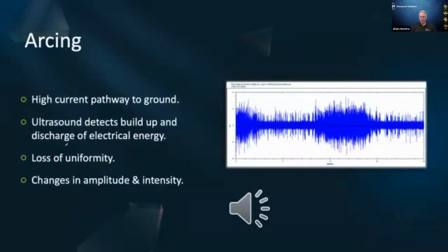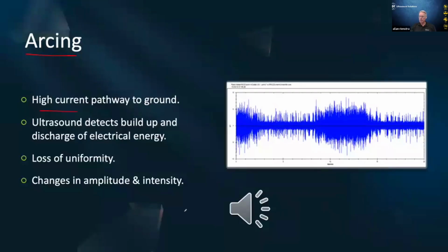I'm showing progressions here. Corona is early stage. Tracking is the next stage. Arcing is what I would call, so if we were to go mild, medium, hot, or a warning versus an alert versus an emergency. When we start getting into arcing, we're now into an emergency stage. That means that the breakdown of the insulating material has become critical. We have a high current pathway to ground. And ultrasound detects the buildup and discharge of electrical energy.